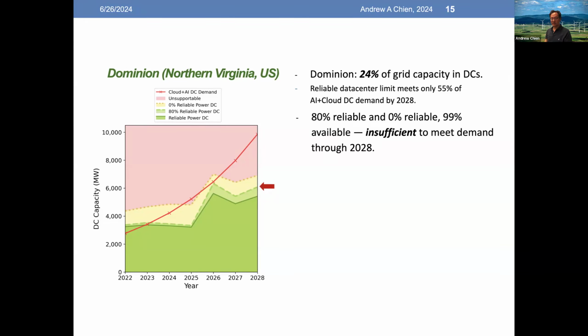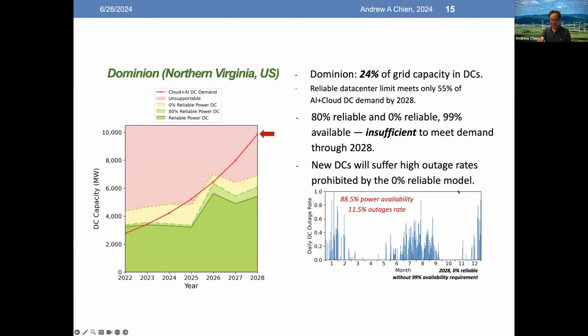And what's worse is if you were to accept that data center 0% reliable, 99% available guarantee, in fact, they could not even achieve the 99% power availability, and there would be like an 11.5% outage rate. And this is the daily data center outage rate. It looks pretty bad over the year. So really, you're not able to get very reliable power at all. So the story is that this increased flexibility is not enough to actually allow you to meet the power demand needs inside of Dominion. So we're in a bad situation there, and there's a huge competition going on about who's going to pay and finance for all this growth, and who can do it fast enough actually to meet this data center demand.